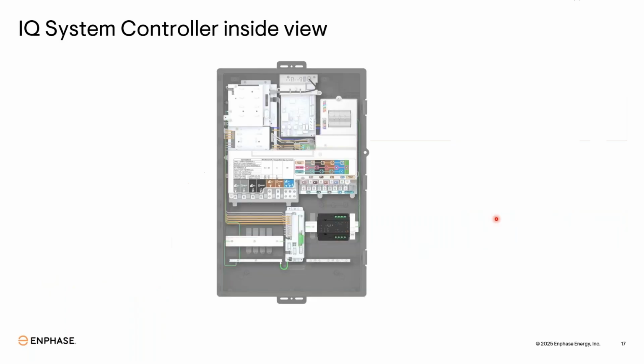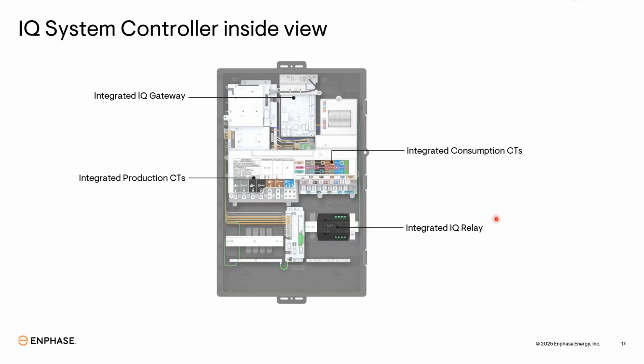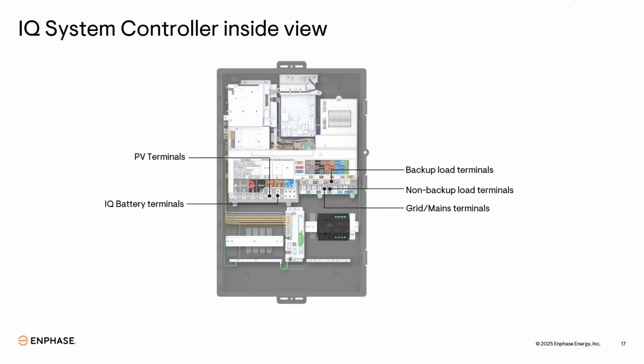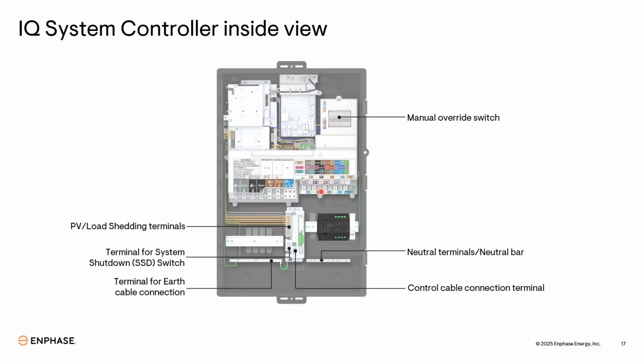If you see the inside view of this controller, this is the inside view. You see the pre-installed IQ gateway there. CTs are installed. The production CTs are here at the PV input, and the consumption CTs are inside at the consumption mains grid input. The relay is here. These are the PV terminals and battery terminals, and these are the grid, backup, and non-backup terminals. This is the manual override switch for bypassing your controller in case of emergency.